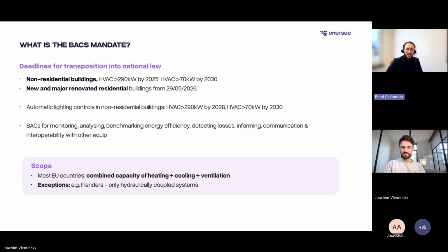Basically, there's a deadline that's already passed: for non-residential buildings with HVAC above 290 kilowatts, you had to have a BACS by 2025. The scope increases to BACS above 70 kilowatts by 2030. So it's a good signal for all of... This is the power, right, not your actual consumption? Exactly, this is the nominal rated power, the max power, the rating power of the installation. That's an important distinction, because a lot of those systems only run at that rated power from time to time, and are often well under it if they're well managed.